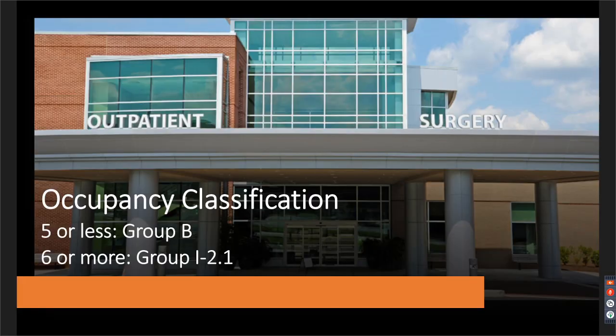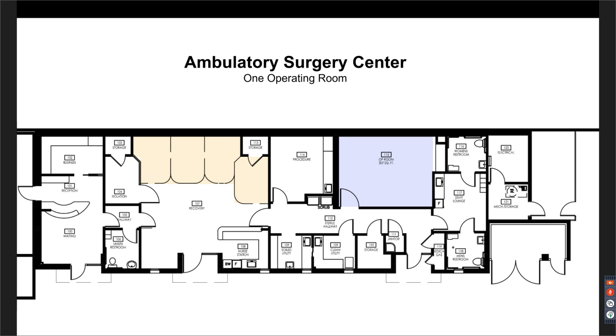So as we figure out how many people we should count, because obviously all of the buildings that we looked at have more than 5 people in them, the occupancy has 5 or fewer patients who are incapable of unassisted self-preservation, or 6 or more patients, not the total number of people in the building. As a rule of thumb, the State Fire Marshal has ruled that if you have one operating room, the code requires that you have a pre-op room. So every operating room requires a pre-op room where that patient may be sedated or incapable of unassisted self-preservation. So now for every operating room, I have 2 patients.